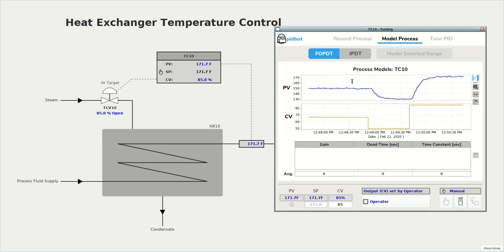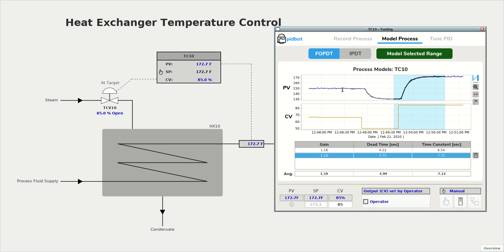So we're going to start our model at a time where the process is at a steady state. And we'll just drag over across our first bump test. We can model that range and we can model the second bump again, starting at steady state. And if we want, we can do a model of both bumps together. And down here we have our process models and the average process model.